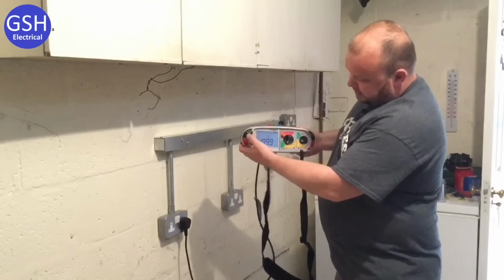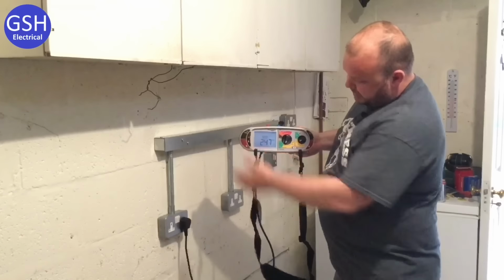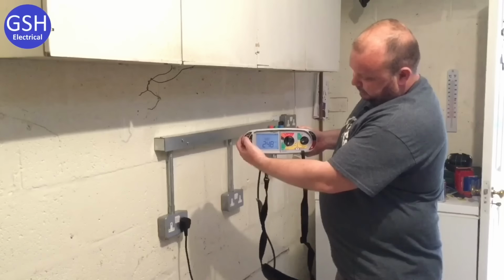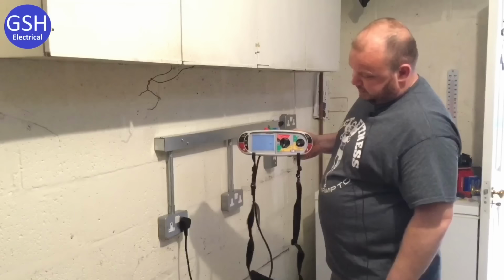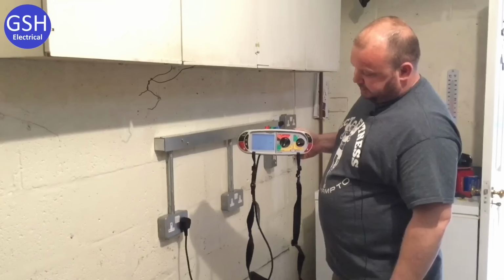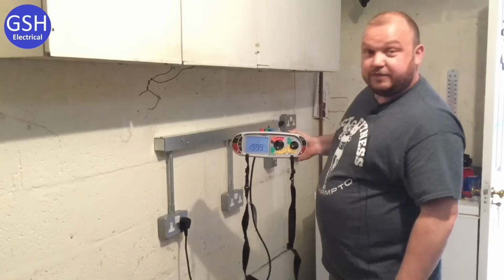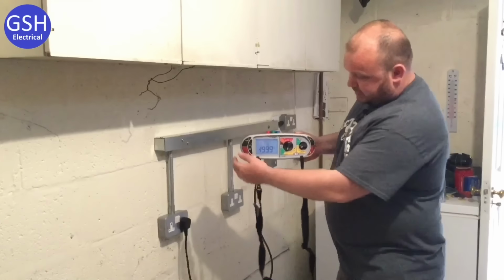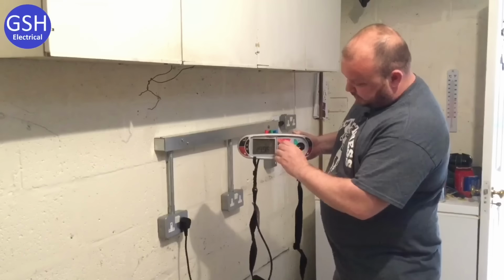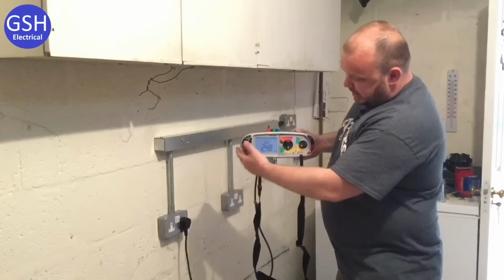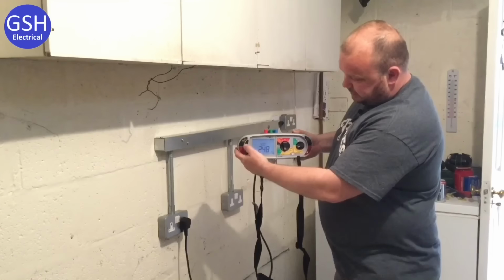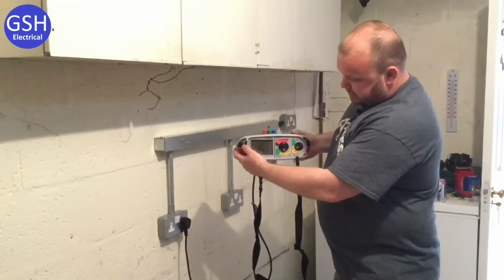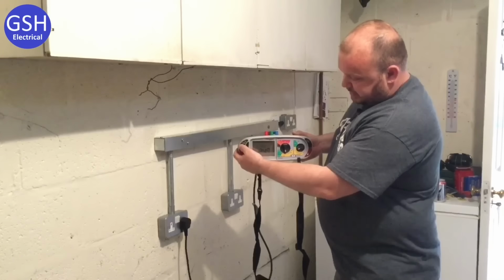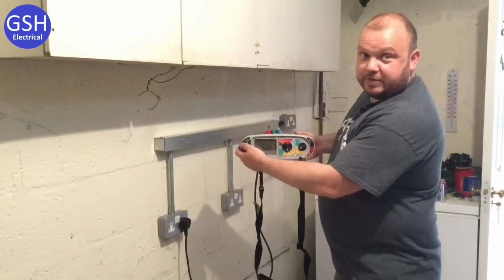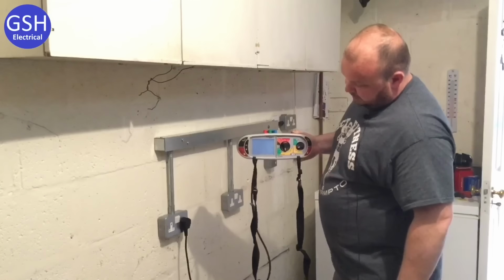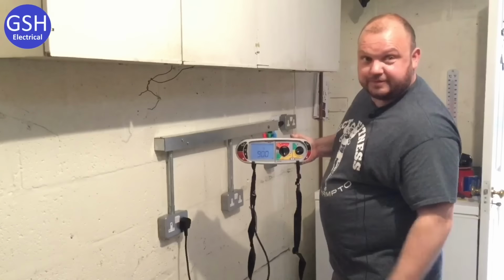I'm going to change the degree to 180. Okay, brilliant. And what do you expect to happen this time? Nothing to happen. Why are you checking it at 15 milliamps when it's a 30 milliamp RCD? Checking it for nuisance tripping. Okay, brilliant. So I've done that. Now I'm going to change it to 1 times. Okay. So that's 30 milliamps being passed through at 0 degrees. Do you agree? Yeah. What's the maximum time the RCD should trip within? This should trip within 300 milliseconds. Let's see what it does. And it's exactly 9. Oh wow, that's quick.